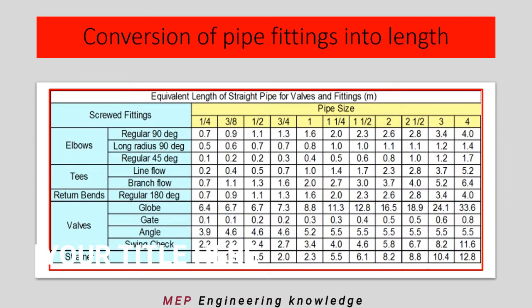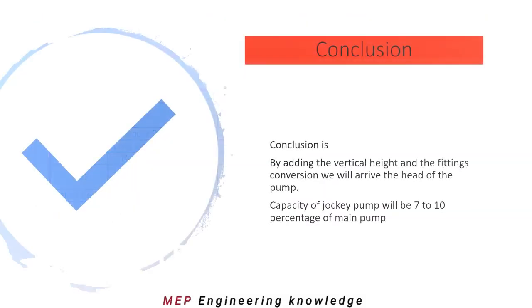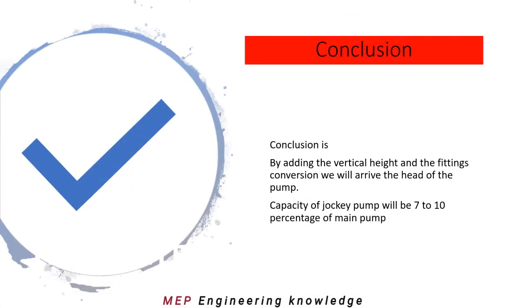Sample details are given — depending on the type of pipe and manufacturer, they will provide this in detail. Using this chart, you can convert fittings losses into length in meters. You can convert elbows, tees, return bends, valves, and strainers into equivalent length, which is then added along with the vertical length to achieve the total head.